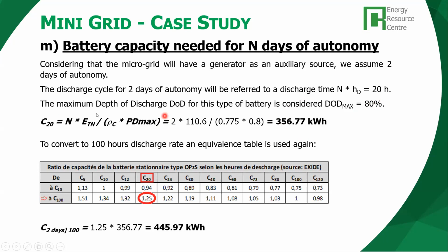The formula we saw, which I have already explained to you in the battery session: number of days of autonomy, and then again we repeat the energy we need from the nocturnal fraction, the efficiency in the consumption, and the depth of discharge maximum 80%. Then we get a sizing in C20, that is the capacity we want from the batteries, the discharge period of 20 hours, of almost 357 kilowatt hour. Again, this is the capacity C20.